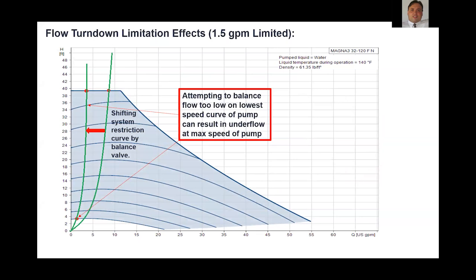So, if you start looking at this with common potable DC direct commutated pumps, you can see some challenges. This is just an example of a Magna 3 pump, which is a potable rated pump, where if we were selecting this for say 8 GPM at its maximum speed curve, and then having to balance this with just a single balance point to achieve this ultra low flow turn down at its lowest minimum speed, you potentially run into issues when you're near the end of that tank charge cycle and not being able to get up to that maximum flow rate, in this case around 8 GPM, because you're dealing with two system restriction curves on your pump.